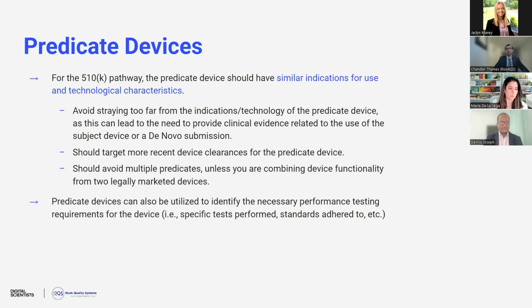One of the things the FDA has come out in recent months and put more of a focus on is making sure that the predicate devices that you're identifying are recent and relevant. So FDA's continuously updating their guidances and what they expect manufacturers and developers to provide to be able to review their device. As part of that increased scrutiny that they've put on year after year, they want to make sure that the device that you're using as your predicate device is more recent, so that way they know that that device was reviewed in accordance with more recent guidances.